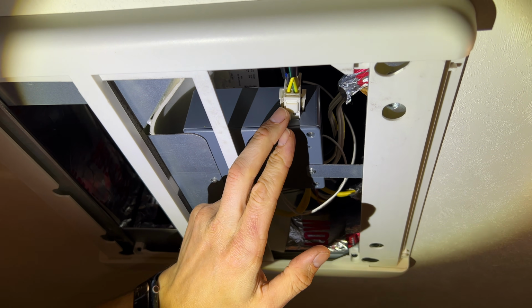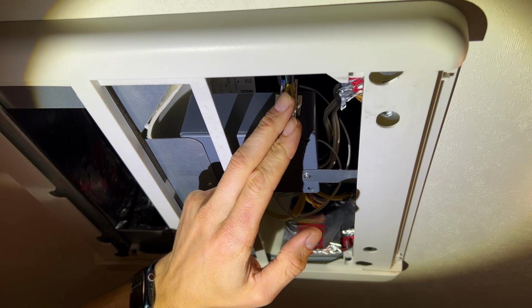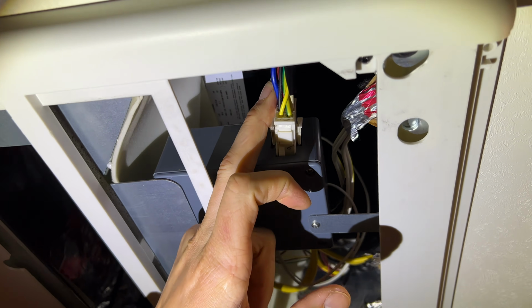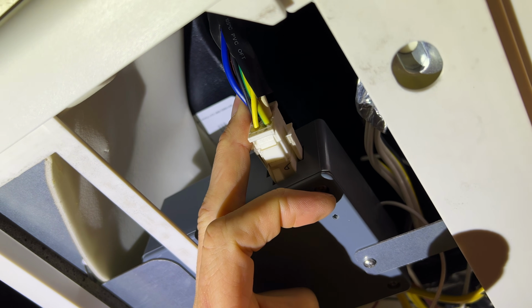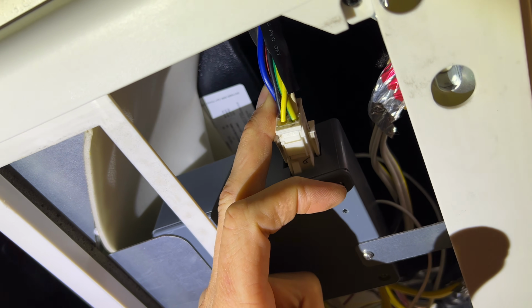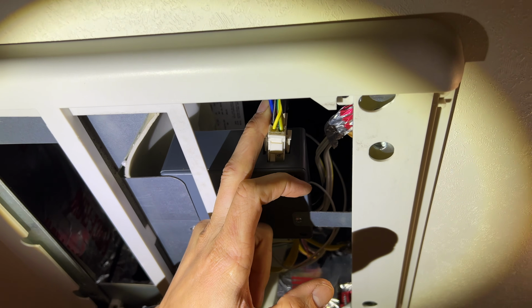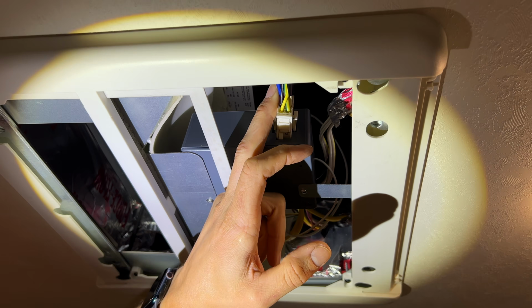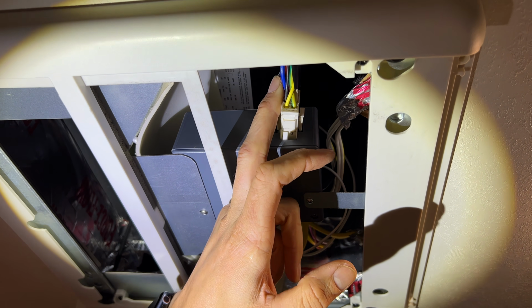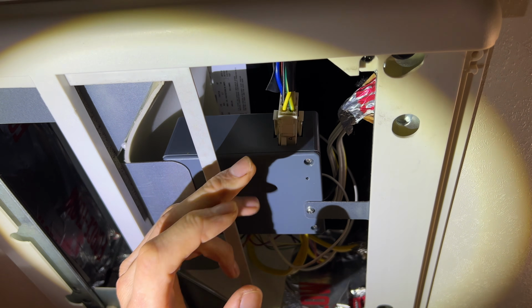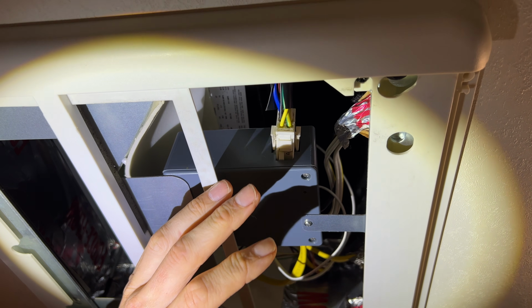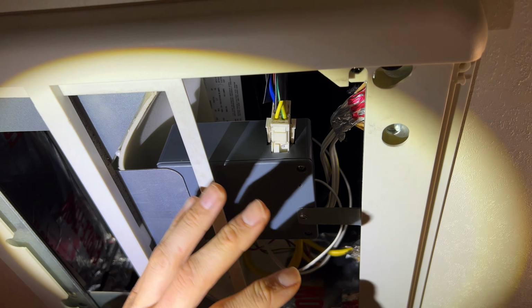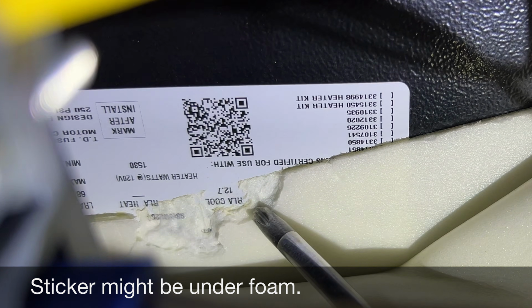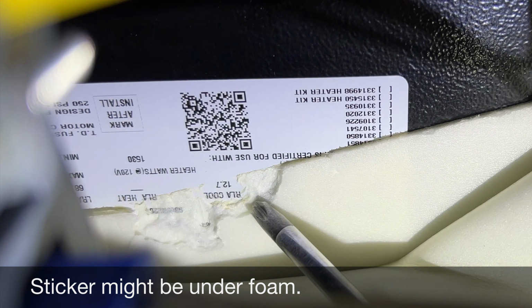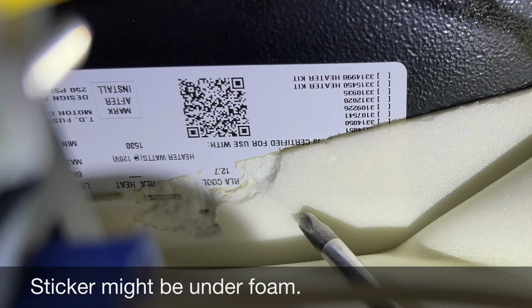On Dometic, you'll have a rectangle 6-pin connector. You look at the wires in there, you'll see a blue wire. That blue wire is going to the compressor. So that's where we'll put our multimeter, setting it to amps AC. When the AC unit is on cool, that should read amps on it. And the number of amps you'll read is based on the sticker of the AC unit. So come around over this way. If you're looking on the sticker, you look for the RLA cool number. So this one says 12.7.